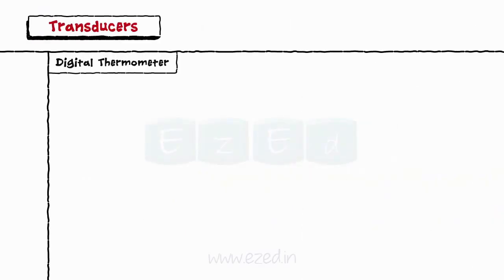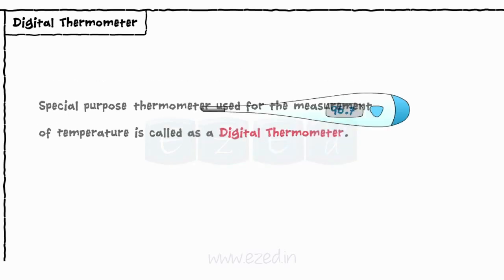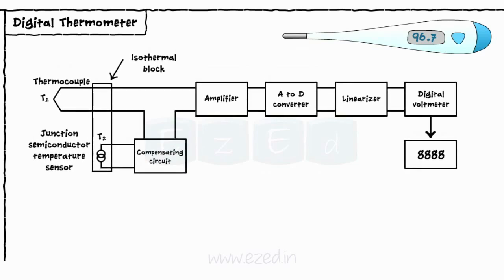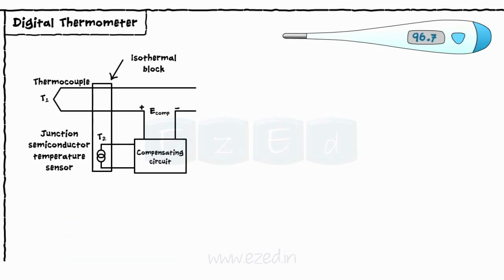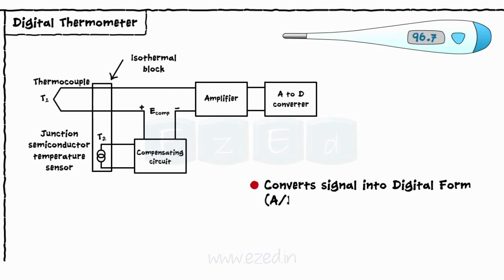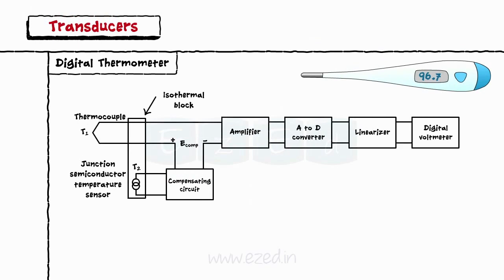The last thing we will study is a digital thermometer. A special purpose thermometer used for the measurement of temperature is called a digital thermometer. The block diagram of a digital thermometer using a thermocouple is as shown. As we are using a thermocouple, we have two measuring junctions T1 and T2. Wires from junction T1 are screwed directly to an isothermal block terminal strip. The temperature T2 of this block is measured by a sensor and applied to the compensating circuit. The compensating circuit produces a voltage proportional to temperature T2, which is in millivolts. It is applied to an amplifier which amplifies it to a desired level. This amplified voltage is passed to an A to D converter which converts it into digital form. This digital voltage is then linearized by a linearizer and applied to a digital voltmeter which gives the direct digital display of temperature T1.